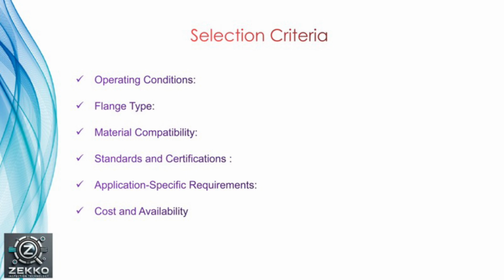The third parameter is chemical compatibility. So the gasket core construction, inner, outer, and the filler material, should be chemically compatible with the system requirement. It shall also be chemically compatible with the process fluid to prevent degradation or failure. Now the second criterion is flange type and surface finish. For flange type, we should ensure the gasket matches the flange design like flat face, raised face, tongue and groove. Another parameter is surface finish. The flange surface finish should be within the recommended range to ensure proper sealing.